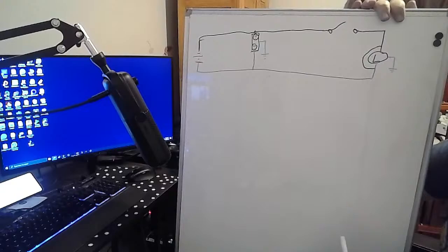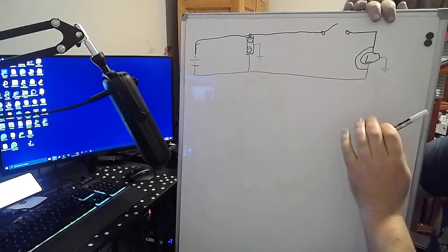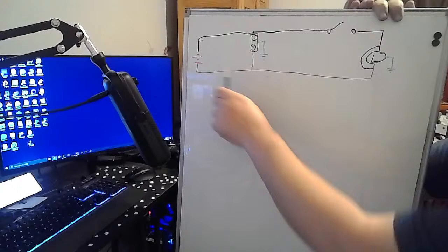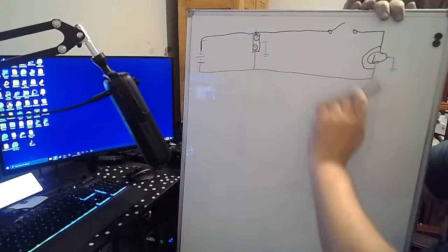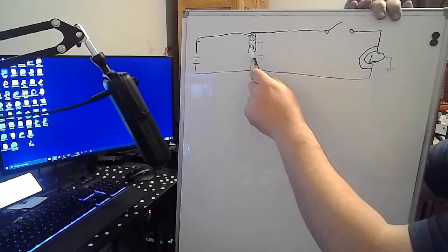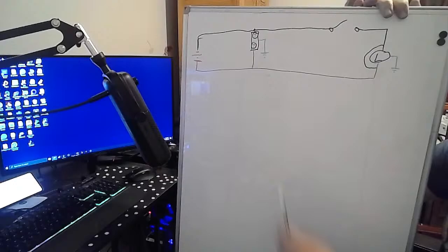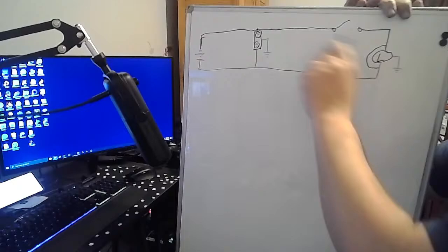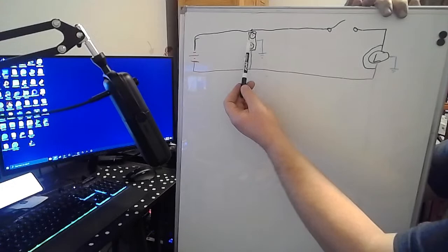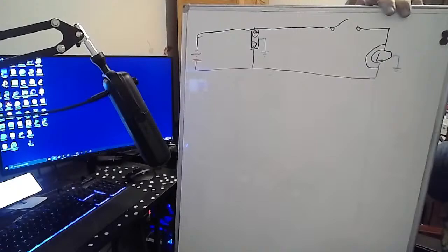And so this is a very basic circuit. Anytime something like this is put into practice, if there's a problem, it's just finding, okay, what's first in the line? All right, this is the first in the line. So if you have a short circuit, you can disconnect this switch and this light and then use your multimeter to check for a short circuit here. And if the short circuit still exists with just this connected, then you know it's not from here over. If you disconnect these two and the short circuit goes away, then you know that it's not here. It's somewhere between here and here, or there. Anyways, you get the idea.